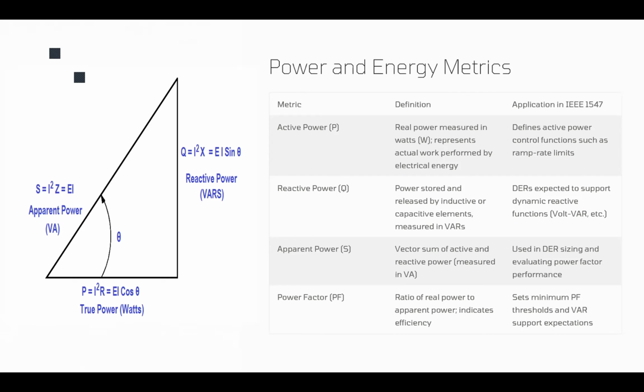Now, when we have active power and reactive power, we can define apparent power, which is the vector sum of those active and reactive power. You can see in the image in the slide how those active, reactive, and apparent power relate to each other. Basically, the magnitude of the apparent power is the square root of active power squared plus reactive power squared. This apparent power is used in IEEE 1547 for DER sizing and the power factor verifications. We're going to talk about that.